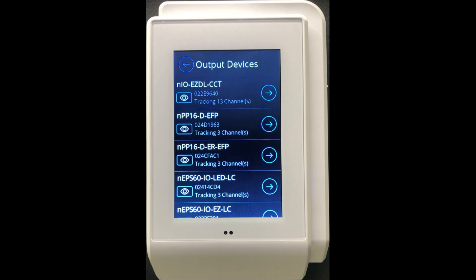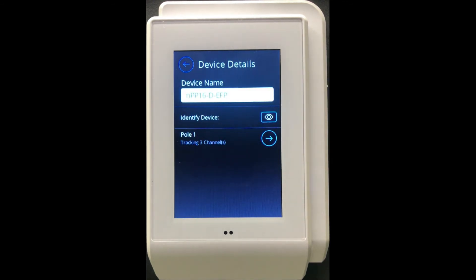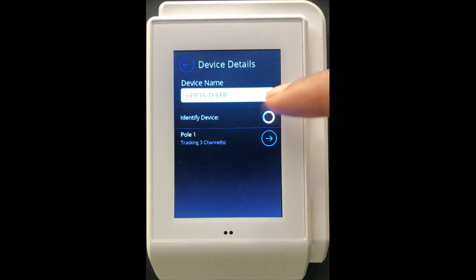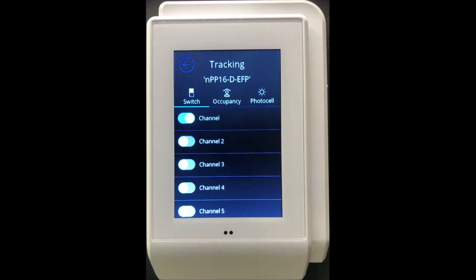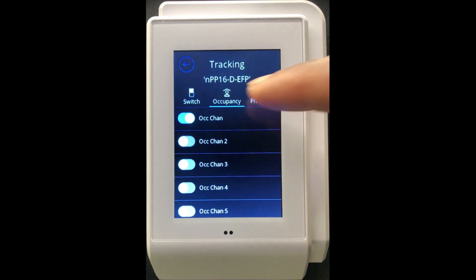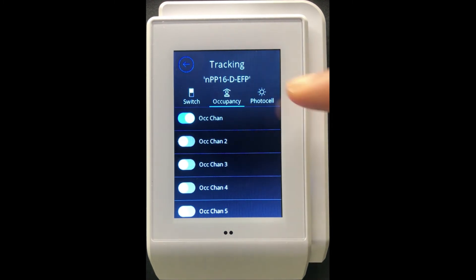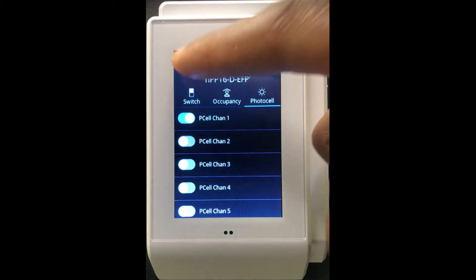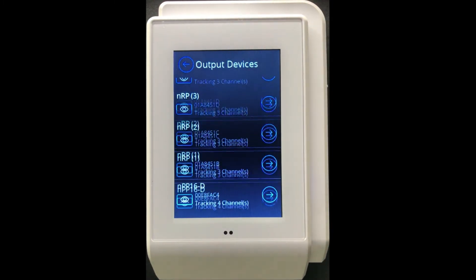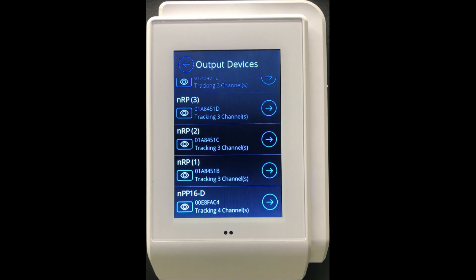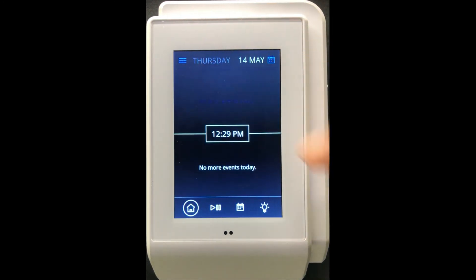By going back, we are pushing these settings accordingly. You also have the ability to configure other output devices — for example, an NPP 16. I can identify this NPP 16 by tapping the identify button; you should hear relays clicking, and that clicking corresponds to the relay for this particular NPP 16. I can then associate which switch channel, occupancy channel, and photocell channels this NPP 16 is tracking. You can continue doing this across all output devices connected to this NDTC, then go back to the home screen.